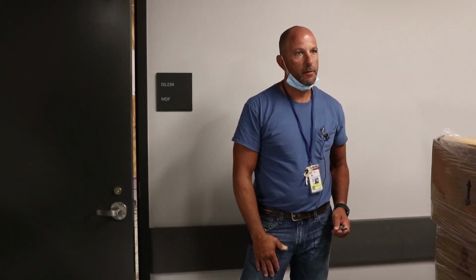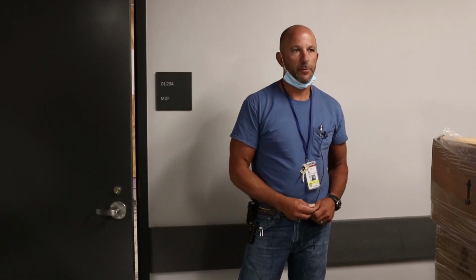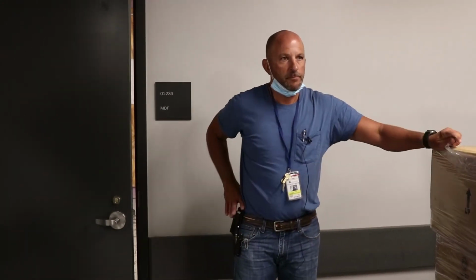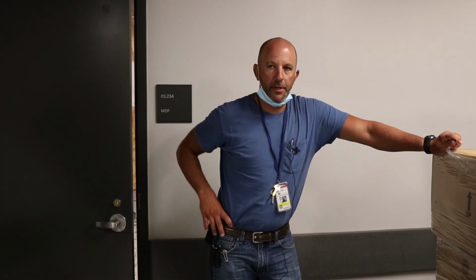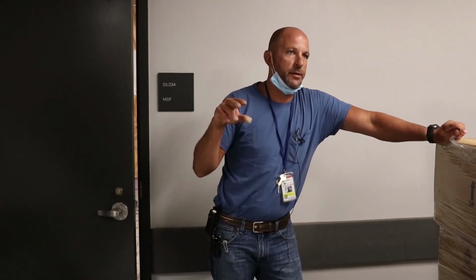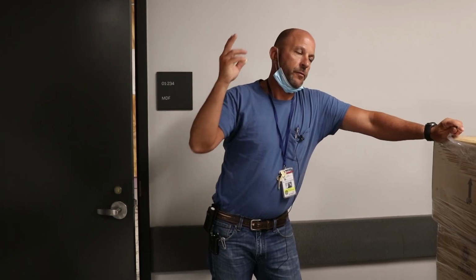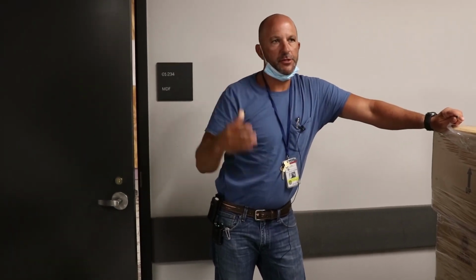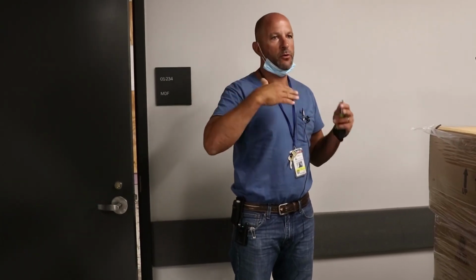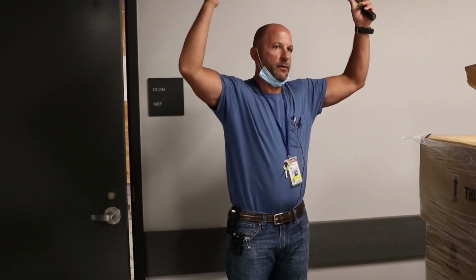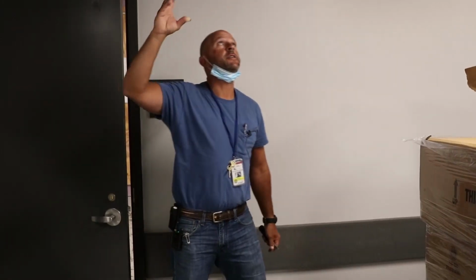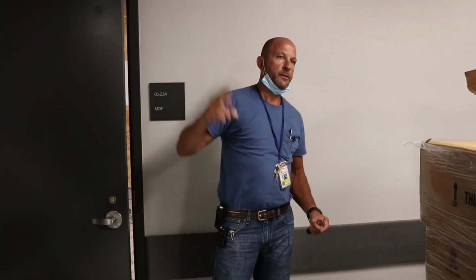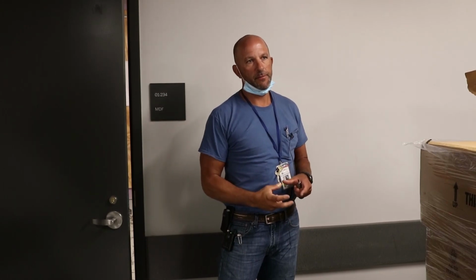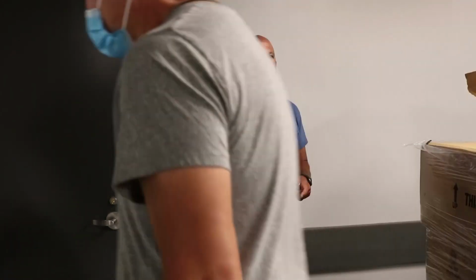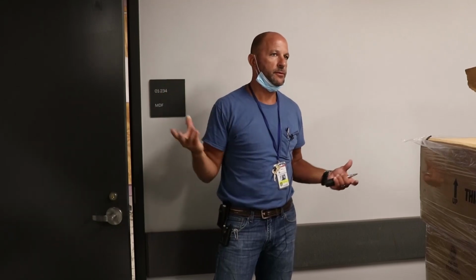How many fire dampers do we have in this building? Throughout the building, over 500. Yeah. So, we can walk a shaft and you can see a riser. If we took air handler 1, for instance, as it rises up the shaft, there's 2 dampers, supply and return, 1 on each side of the corridor. And you can follow that straight up to 5. It's pretty typical. And in every location, you're going to have some kind of LED or indicator that shows whether the damper is tripped, on, flashing, in service.